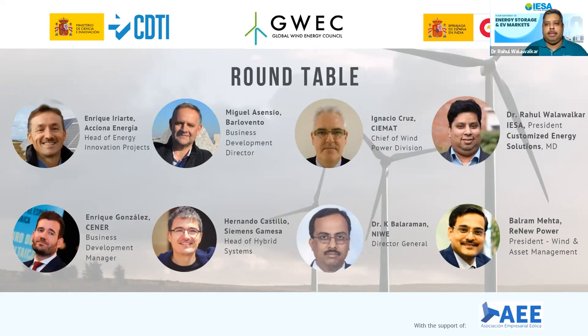If you have some failure where you have two or three air conditioning units and one unit fails, suddenly you realize the rest of the units are not able to take care of the complete heating load. Especially nowadays, most storage battery manufacturers have started putting in very stringent warranty conditions, where some of these conditions can actually void your warranty. So it's very important that you pay close attention to these parameters.